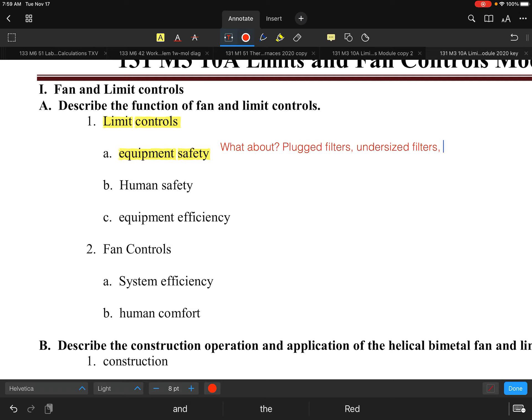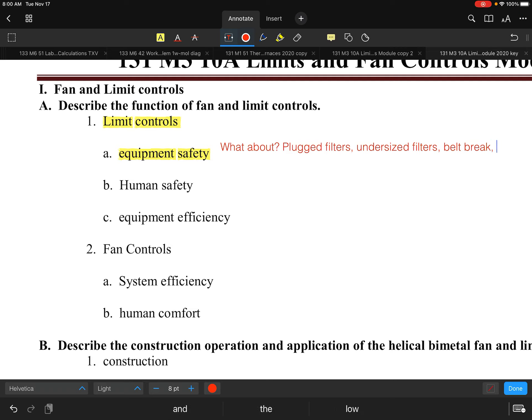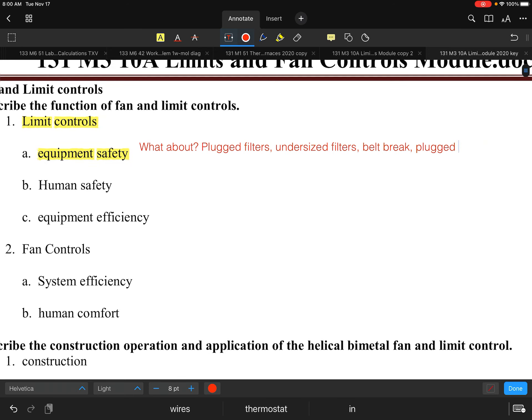Plugged and undersized filters are major problems. On rooftops and some furnaces, a fan belt break is another issue — if the belt breaks, the motor may keep running but the fan won't, so you lose airflow entirely. All of these situations are going to create a high-temperature type of application.